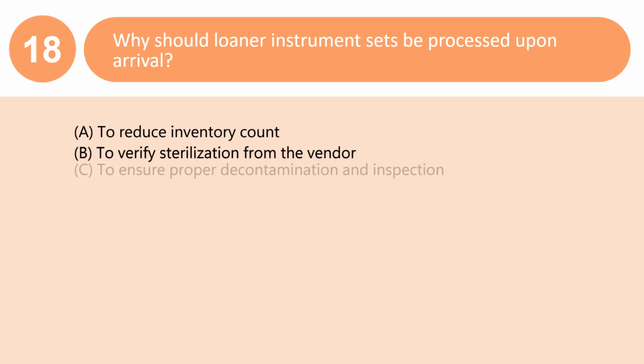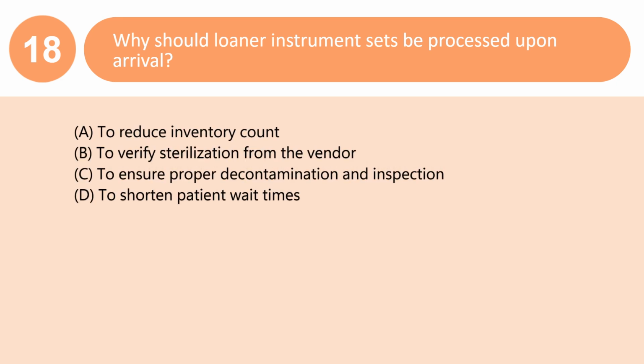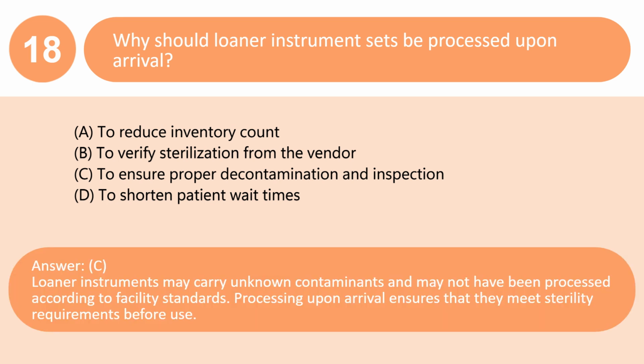Why should loaner instrument sets be processed upon arrival? A. To reduce inventory count. B. To verify sterilization from the vendor. C. To ensure proper decontamination and inspection. D. To shorten patient wait times. Answer: C. Loaner instruments may carry unknown contaminants and may not have been processed according to facility standards. Processing upon arrival ensures that they meet sterility requirements before use.